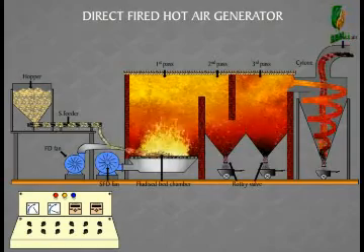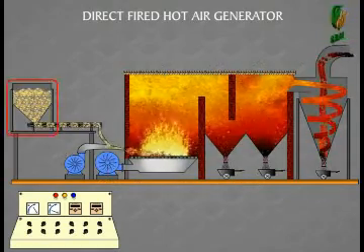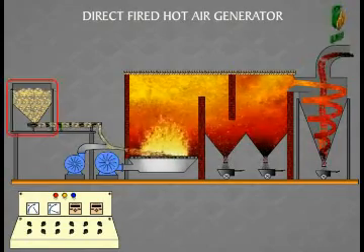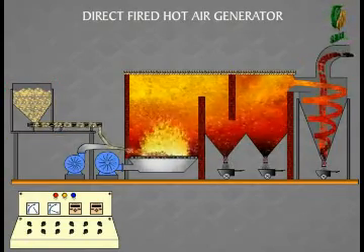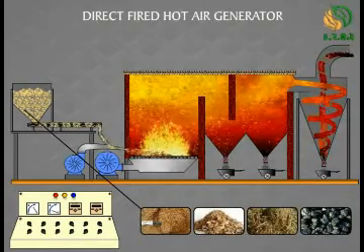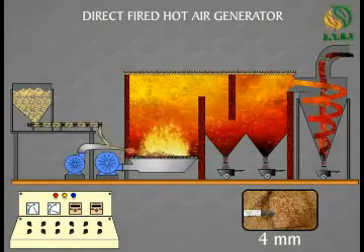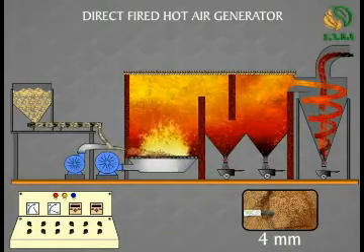The fuel is added into the hopper. This hopper has a capacity to handle 8 hours of lignite or coal fuel. Apart from these, other fuels like bagasse, wood chips, and husks can also be used. The size of the fuel particles is usually kept under 4 mm in size.